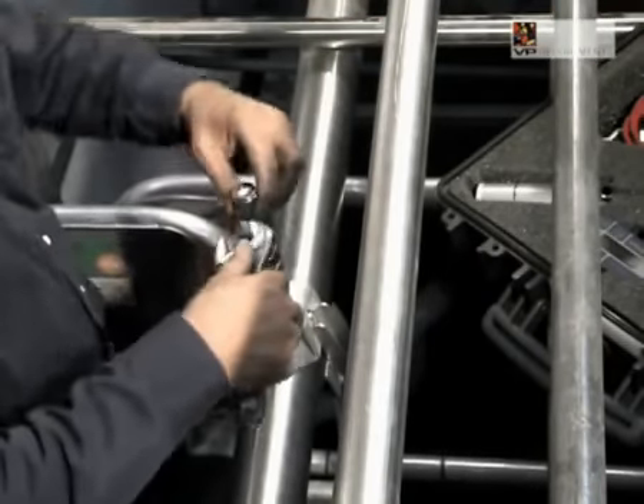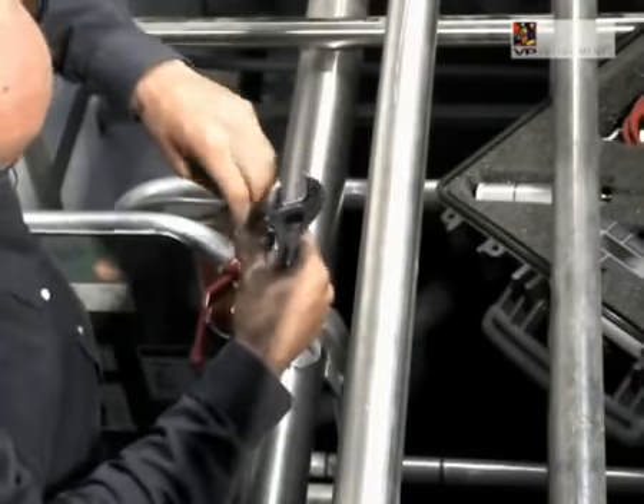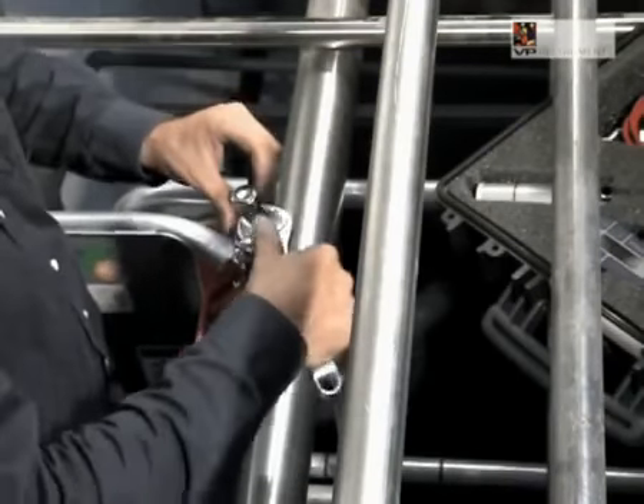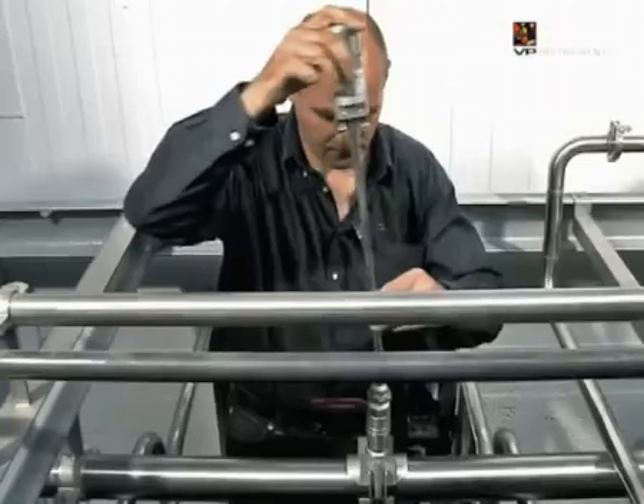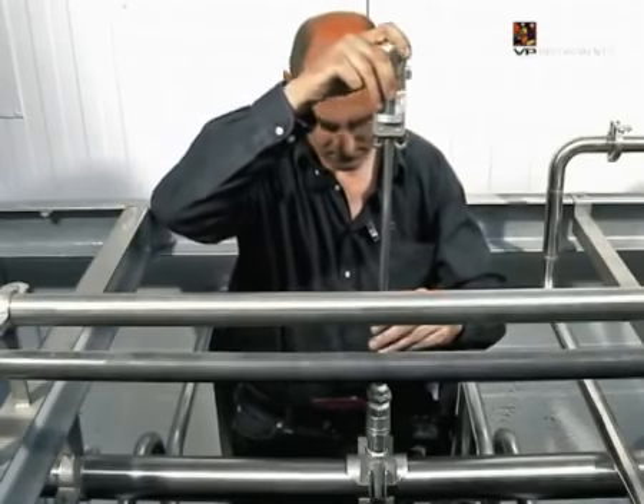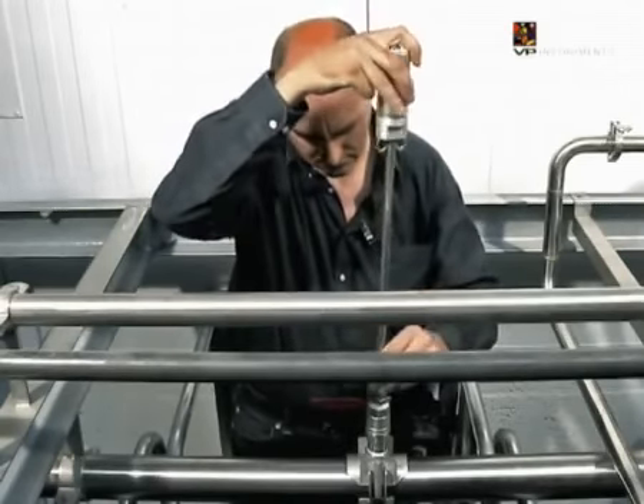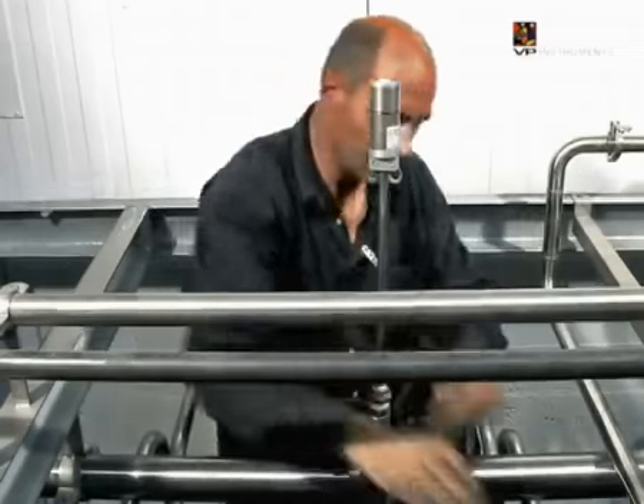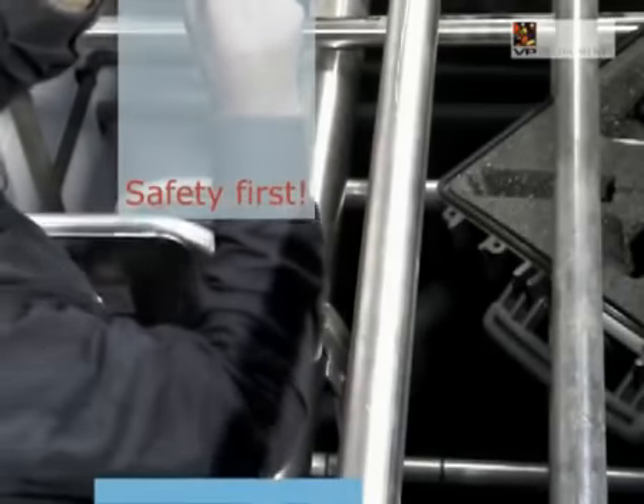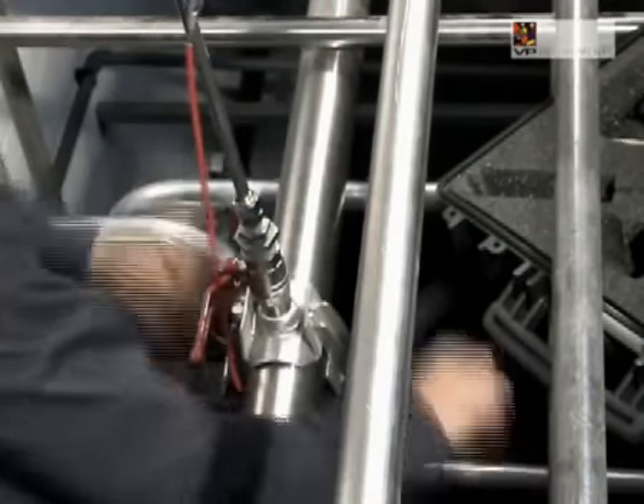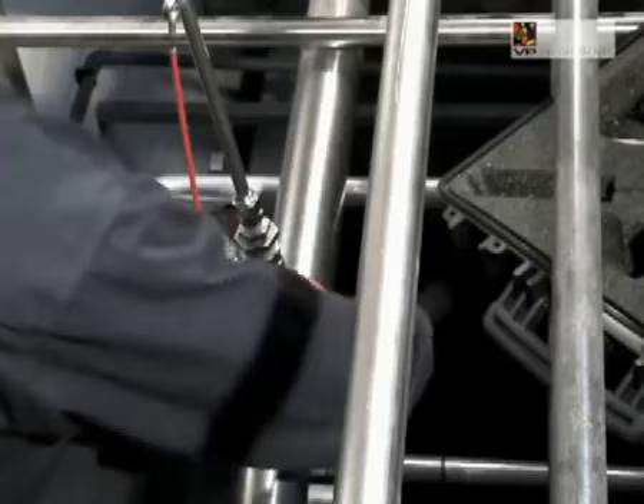After retracting the drill, close the ball valve. Some hot tap tools require a 3/4 or 1 inch ball valve. In this case, you can use an adapter to reduce the thread to 1/2 inch. Insert the compression fitting in the ball valve. Use Teflon tape or liquid sealant to seal the compression fitting.